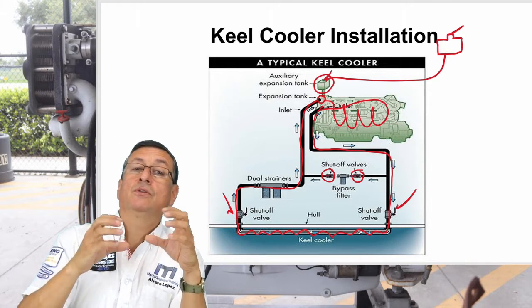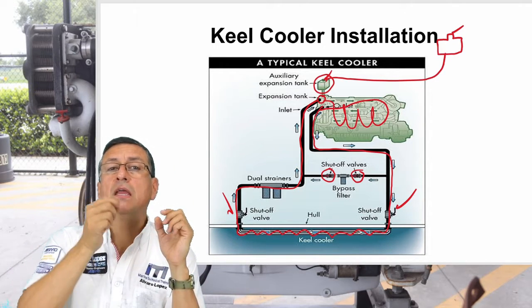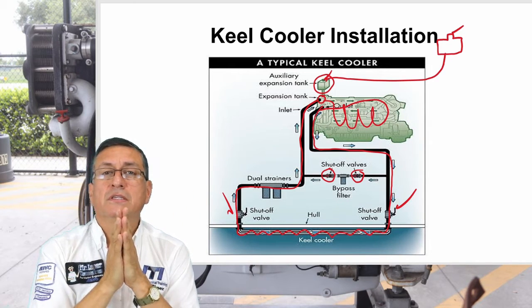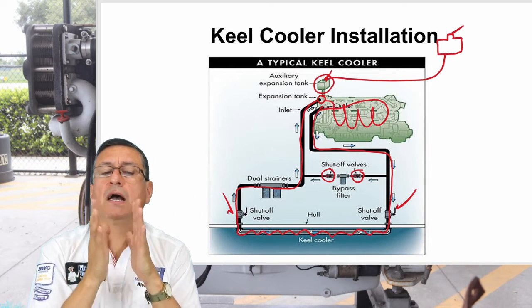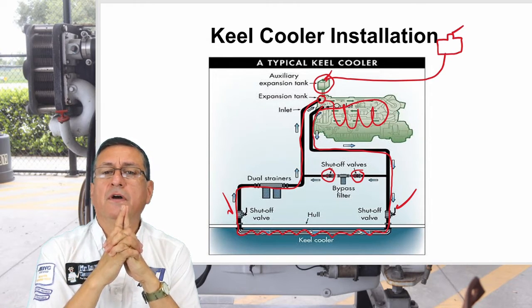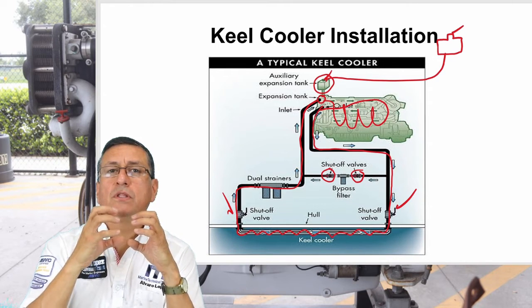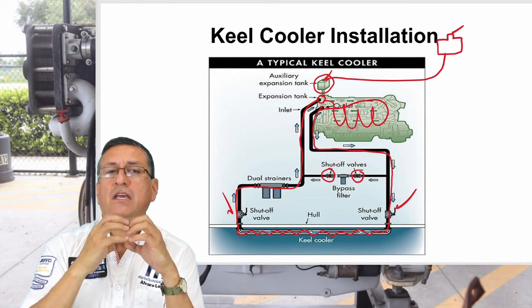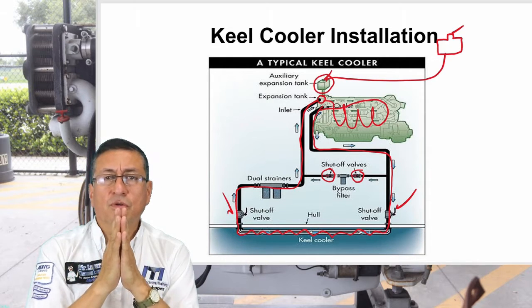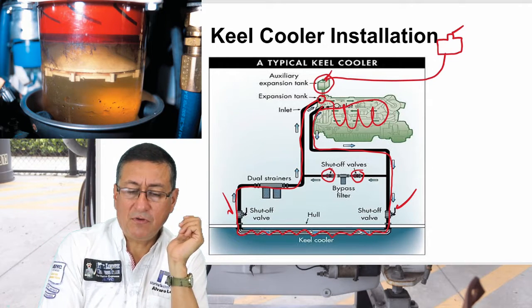And after that we are going to check the coolant pump or circulating pump. No lateral play, no leaks in the bottom hull. Okay, if the coolant pump is damaged, I replace the coolant pump, and I am also going to verify that the pulley on the coolant pump is good, with no play and no indication that the shaft is in bad condition. Okay, this is basically the procedure to check the coolant side. In this system, it's very common to add a couple of filters.